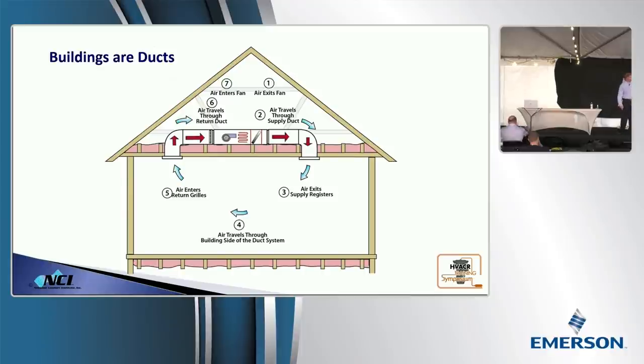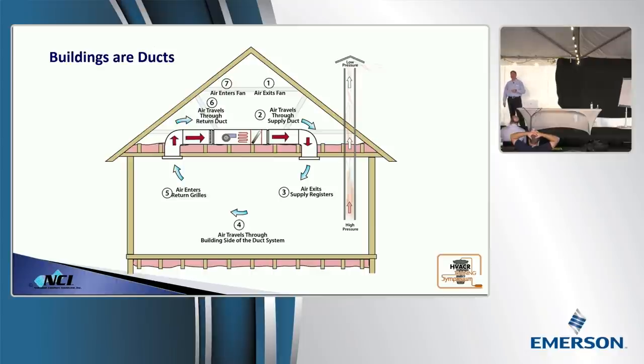So notice that we've got a continuous flow here. The building is what provides the connection from the supply air to the return air. Now, one of the things that we do, if everything's perfect, great. No pressure difference. Now, what we do is we start sticking ducts inside this building part of the duct system. We stick fuel-fired equipment in it. We'll take another duct and we'll stick it through the roof that's wide open. And we'll assume air is going to come down it. And because it's installed according to code, we go, everything's working great. Guys, we're the only industry that's crazy enough to start fires in somebody's house and not test them to prove them and make sure that they're safe. Is that a fair assessment or is that a little brutal? I'm not saying you guys, but our industry in general.